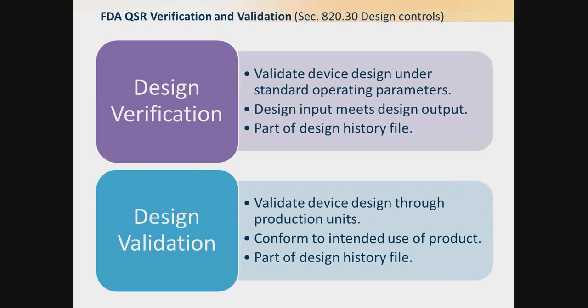Looking at the potential quality system regulations for verification and validation: design verification involves validating the design and the standard operating procedures. The design input is required to meet the design output and forms part of the design history file. Design validation, in contrast, is validating the device through development of production units, confirming that the intended use of the product is a fit for the customer — and this is also part of the design history file.